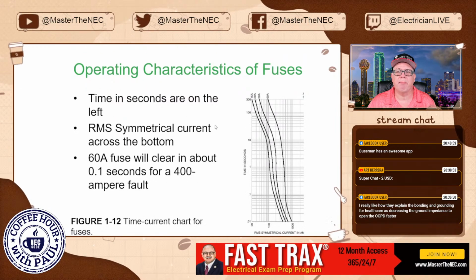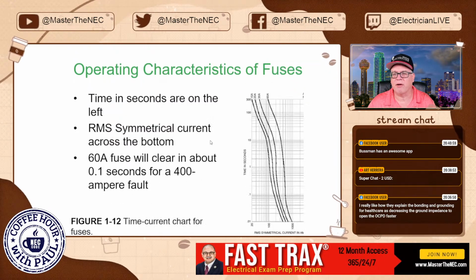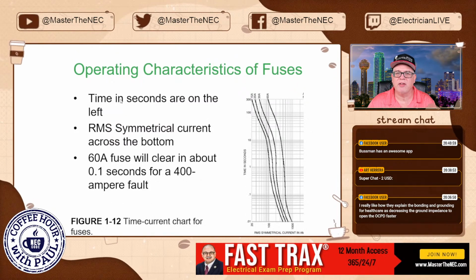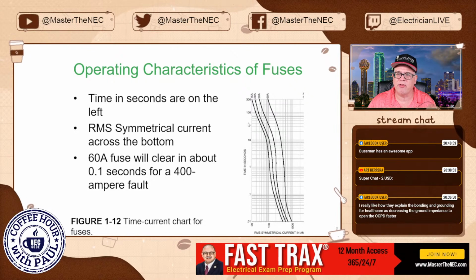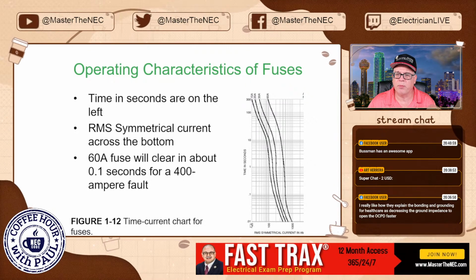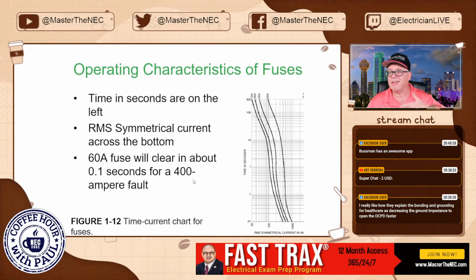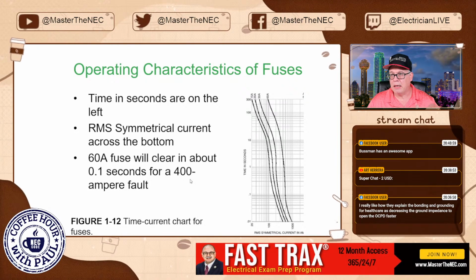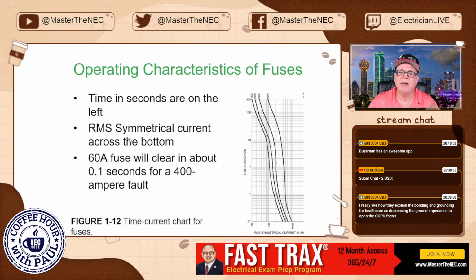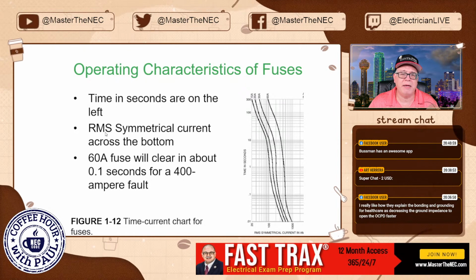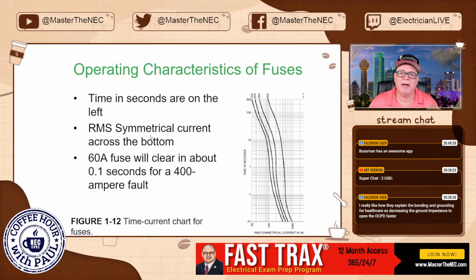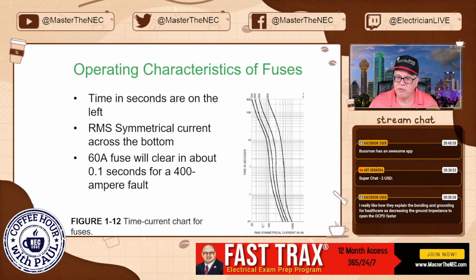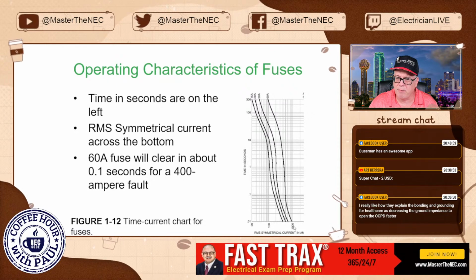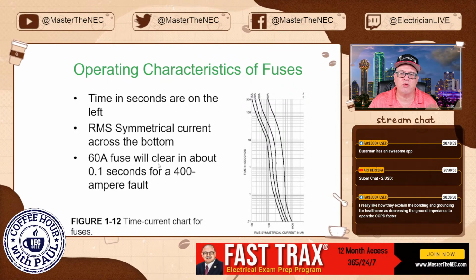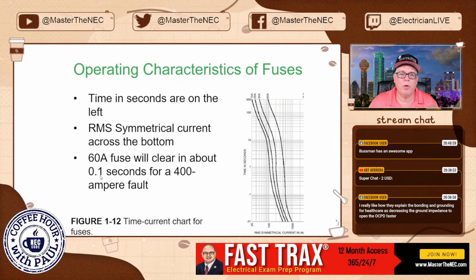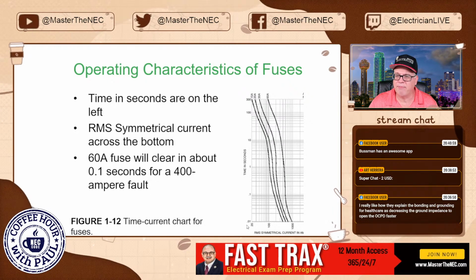Now here you see operation of a fuse, a little different. That's a circuit breaker. So here you see the fuses, times and seconds are on the left. So this is seconds, 0.01, which is, we're familiar with this kind of reference to things like selectively coordinated and whatnot. Then you have what's called the RMS, root mean square, symmetrical current across the bottom. So there it is here. Okay, this is the RMS. And then a 60 amp fuse will clear in about 0.1 seconds for a 400 amp fault.